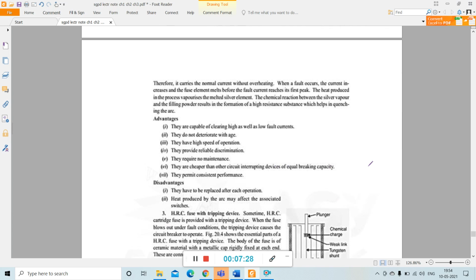The heat produced in the process vaporizes the melted silver element, and the chemical reaction between the silver vapor and the filling powder results in the formation of a high resistance substance, which helps in quenching the arc. So that means when a fault occurs, the silver element melts and vaporizes, and then there is a chemical reaction between the silver vapor and the filling powder, and whatever substance is formed is of high resistance, which helps in quenching of the arc.